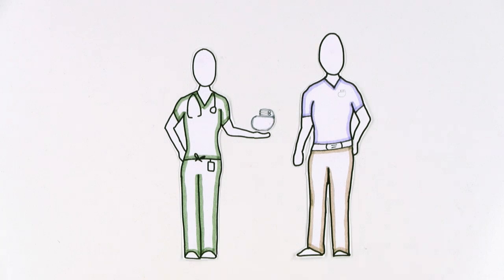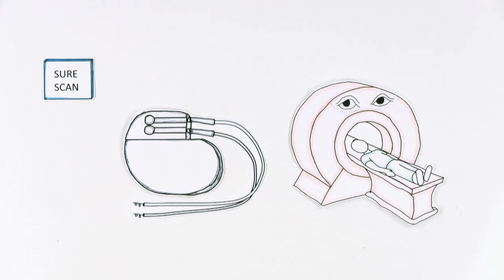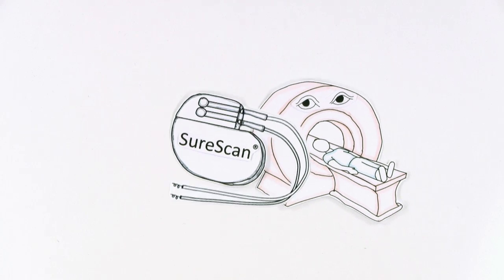She said there is now a pacemaker that has addressed this problem. Medtronic's pacing system with SureScan technology has been specifically designed so that under certain conditions, the pacemaker can be used with MRI.